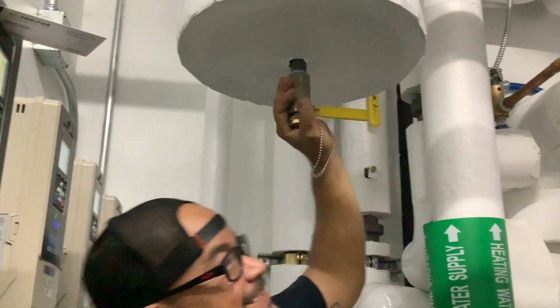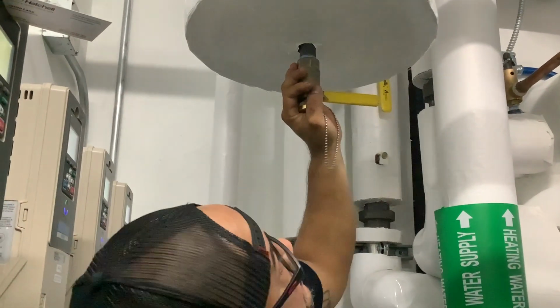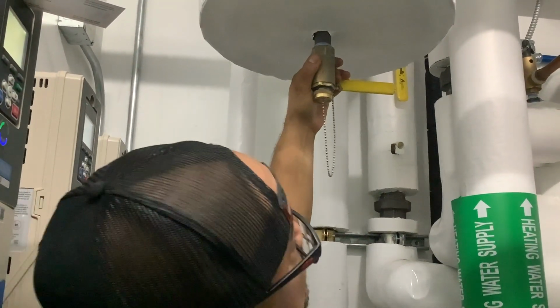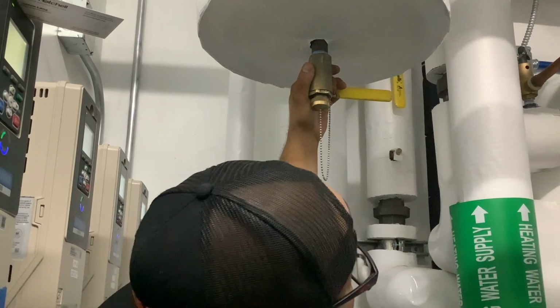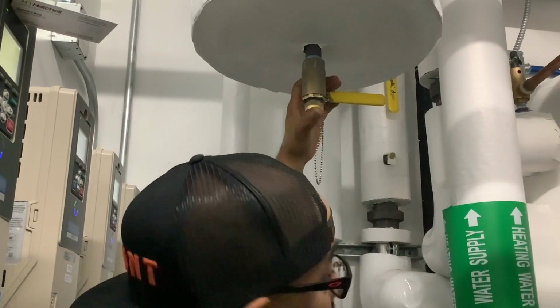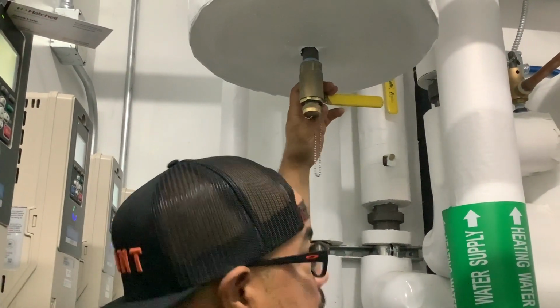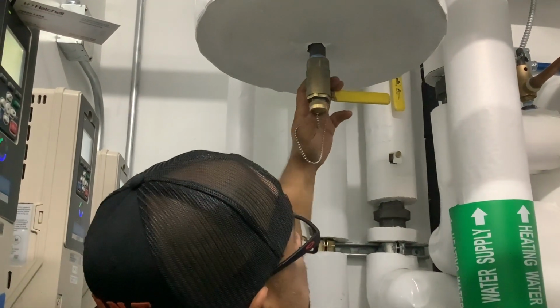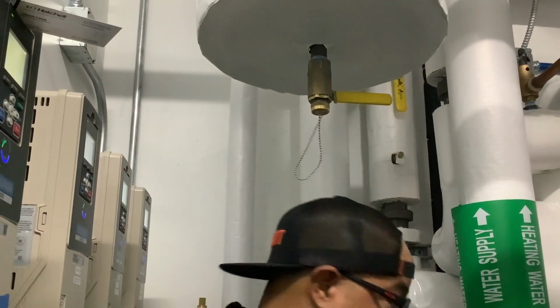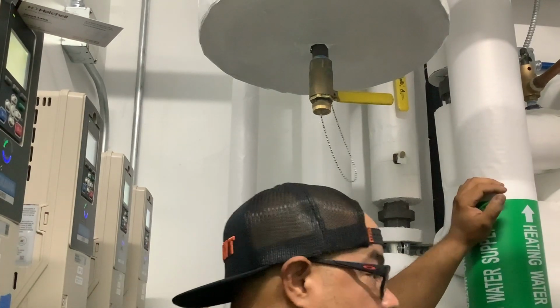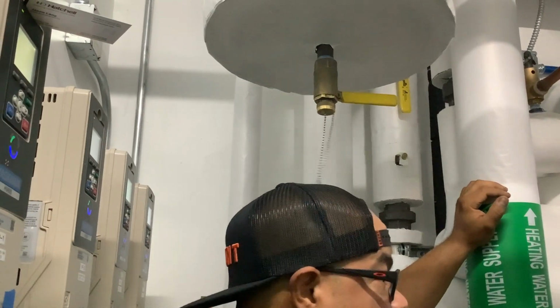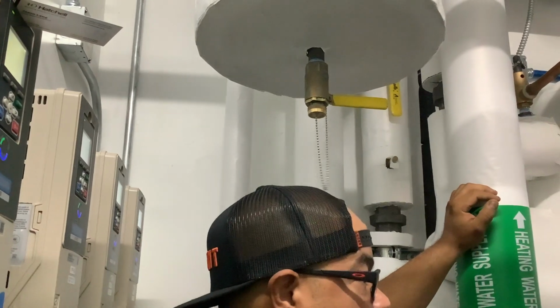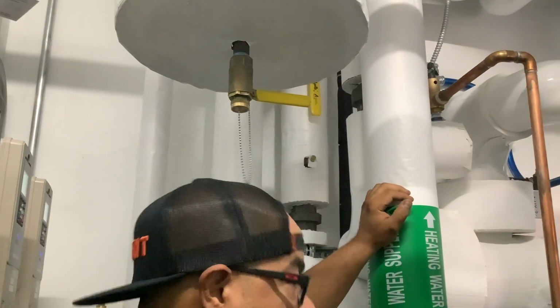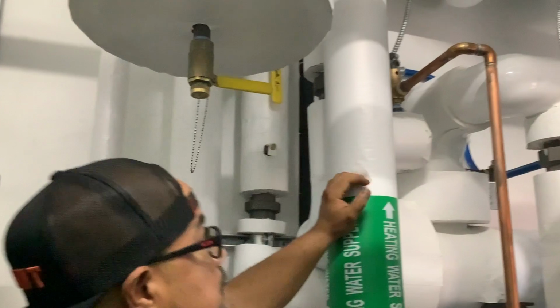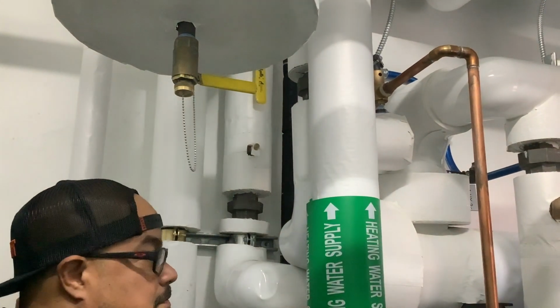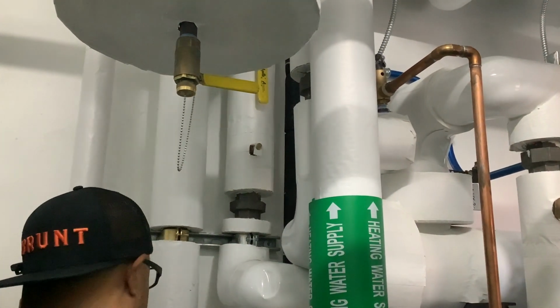That's a serviceman's shower. One thing I'd tell everybody, and I'm sure you already know it, is at least once a year when you're in here doing maintenance, just give it a blowout to make sure it's clear. What that does is get all the garbage and debris out of there, but it also tests a couple other things. It makes sure your air eliminator is going to work, because you'll drop the pressure and then hear it. It also confirms your water fill valve is working too. So it does a few tests.